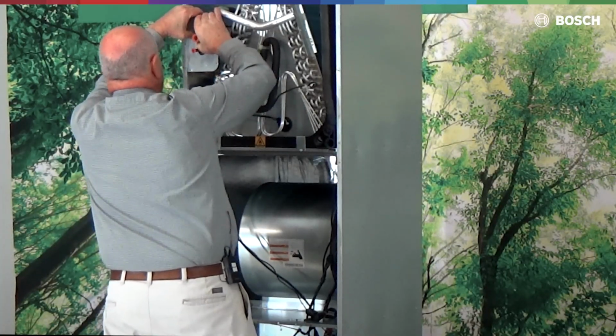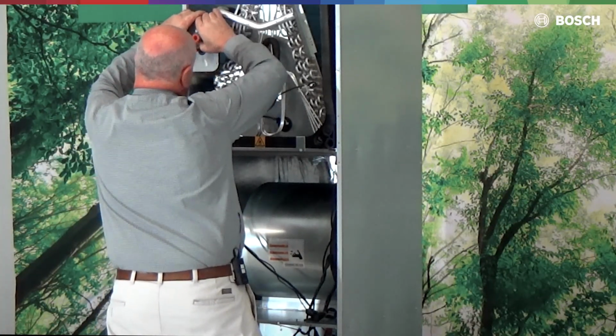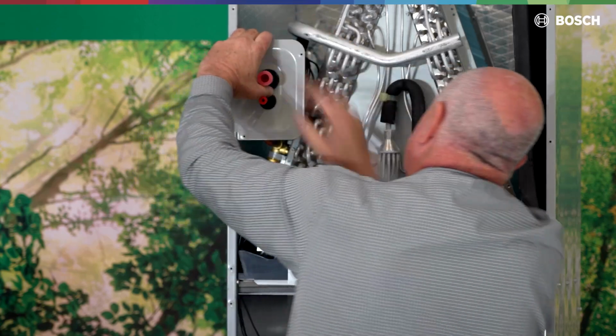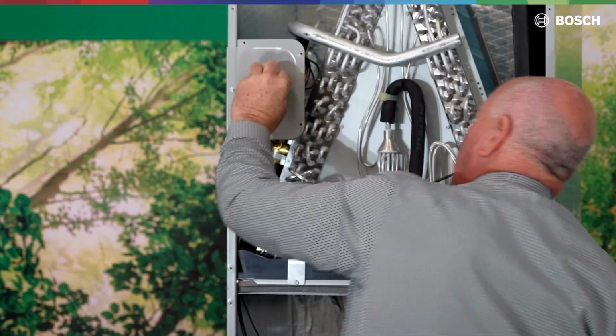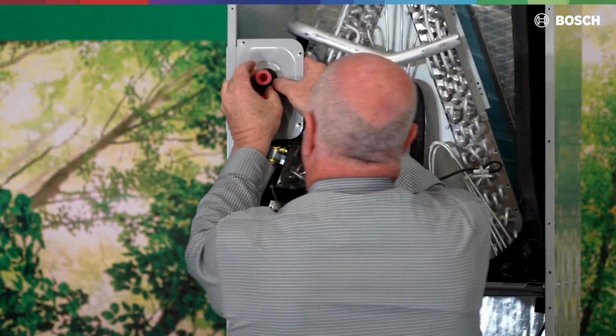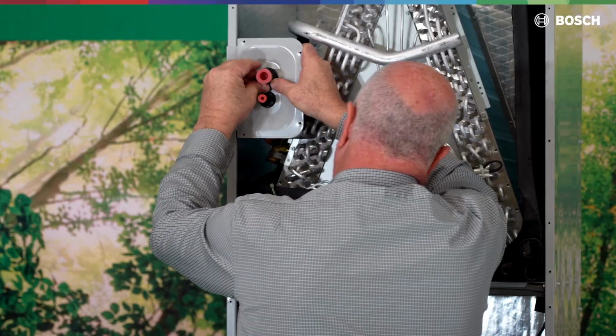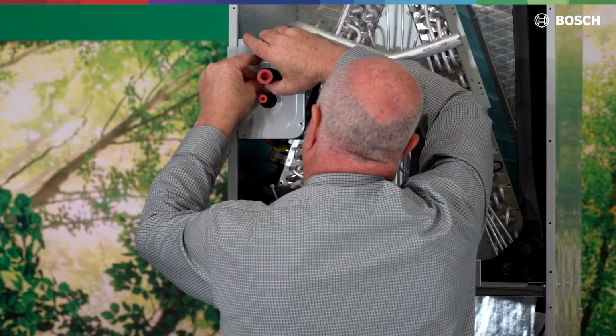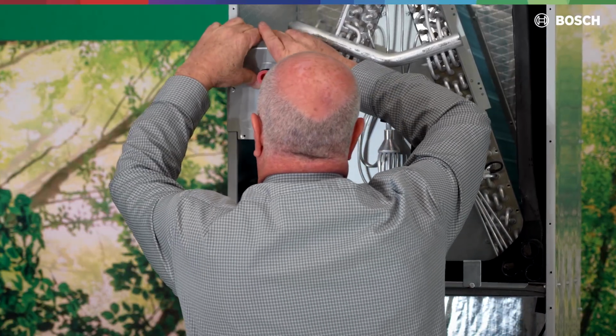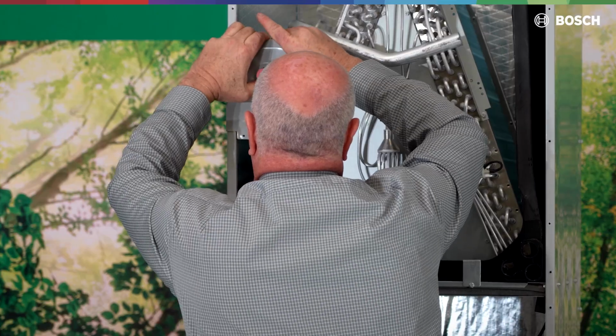Guys, you make your connection. This is probably a good thing to show. When you're making these connections, you want to watch how much heat you put on your braze joint, so that you don't do damage to the valve or the sensors that are in here, to make sure we don't melt anything or catch anything on fire.